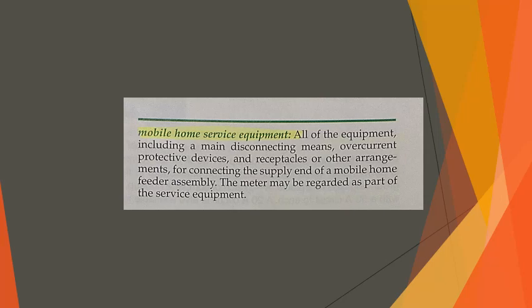The cord, which must always be approved and labeled for mobile home use, must be no shorter than 21 feet and no longer than 36.5 feet from end to end. The plug must be of molded type. The opposite end of the cord must be permanently attached to the distribution panel board in the mobile home.